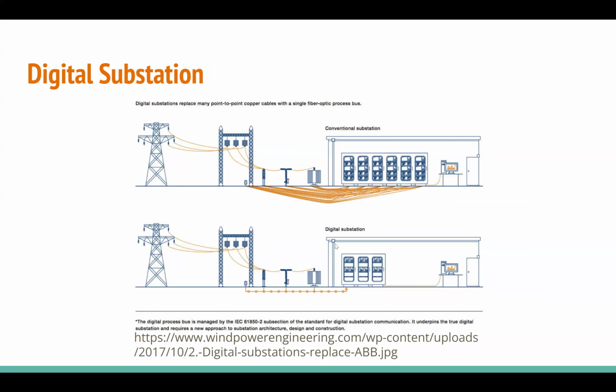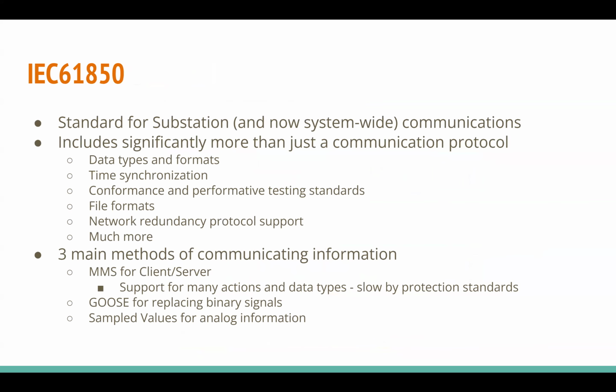In a digital substation, if your Ethernet network goes down, you lose protection, which is the absolute worst case scenario a utility does not want to happen. That's one of the reasons adoption is slow: you've put your critical infrastructure on an Ethernet-based network, and it has to never, ever have a failure. It cannot go down at all.